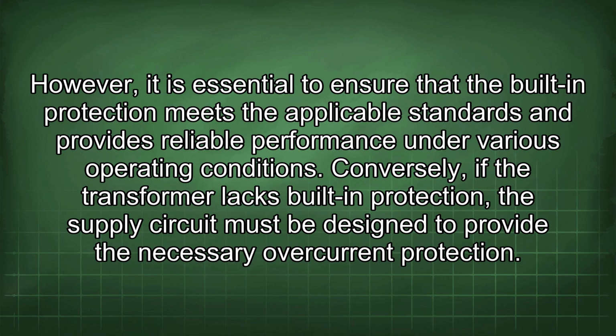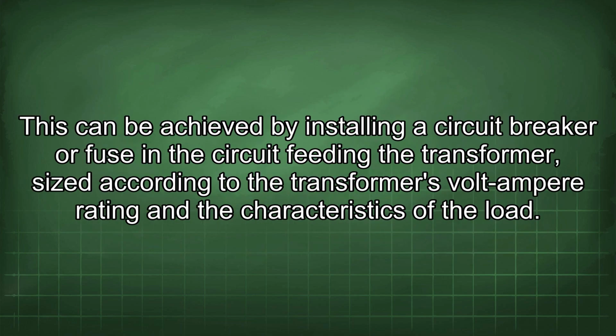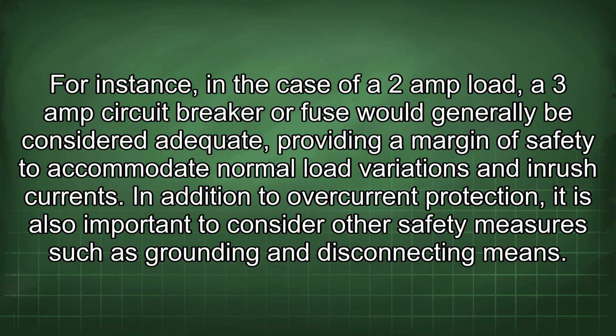Conversely, if the transformer lacks built-in protection, the supply circuit must be designed to provide the necessary overcurrent protection. This can be achieved by installing a circuit breaker or fuse in the circuit feeding the transformer, sized according to the transformer's volt-ampere rating and the characteristics of the load. For instance, in the case of a 2 amp load, a 3 amp circuit breaker or fuse would generally be considered adequate, providing a margin of safety to accommodate normal load variations and inrush currents.